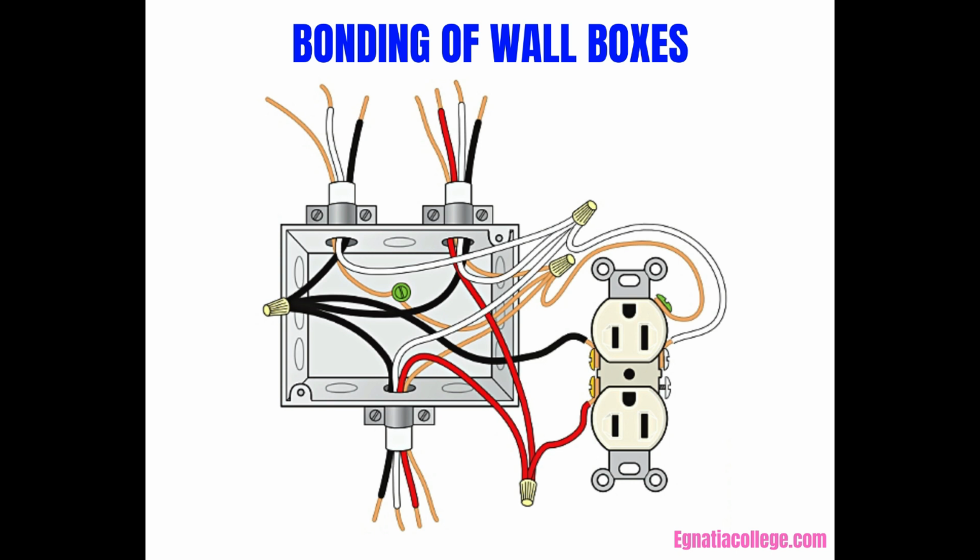According to CEC Diagram 1 and Rule 26-700, grounding-type receptacles must be installed on 15 ampere and 20 ampere branch circuits. This figure shows how to attach the bonding conductor to the proper terminal on the receptacle.